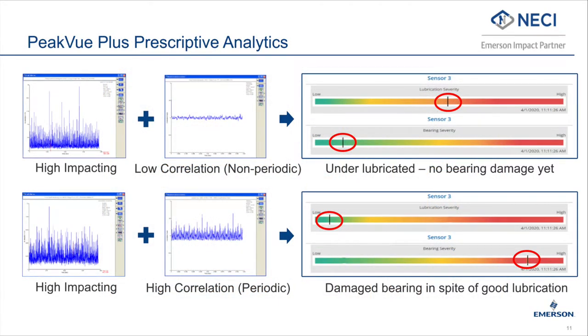The AMS Wireless Vibration Monitor incorporates Emerson's PeakVue Plus prescriptive analytics. This technology differentiates between high impacting that is non-periodic — for example, doesn't occur at the same time each rotation — and periodic, and can provide notification to the user that there is a lubrication problem or there is a bearing fault. This allows a user who is not a vibration analyst to make educated maintenance decisions.